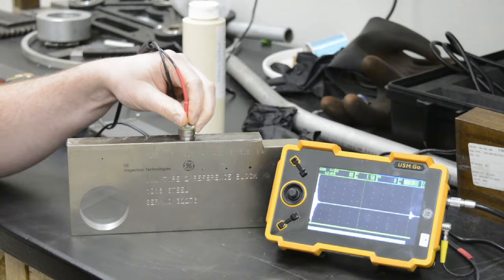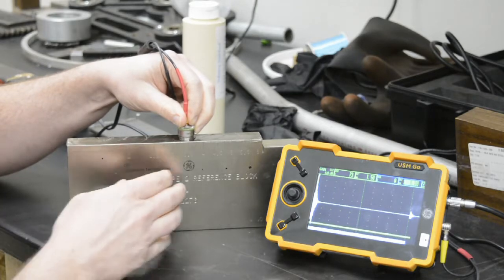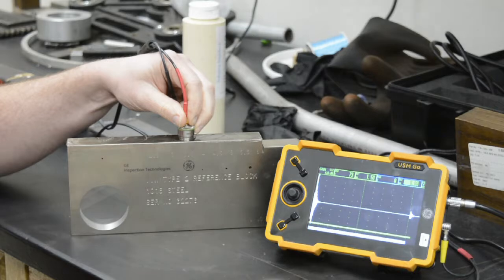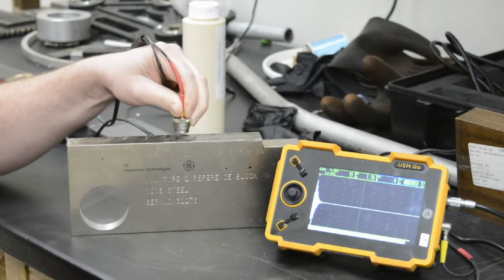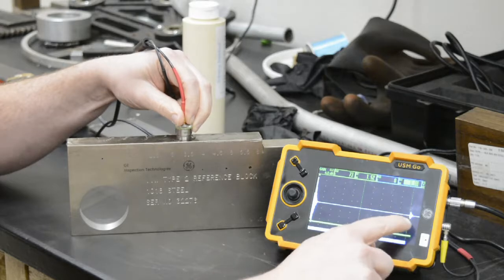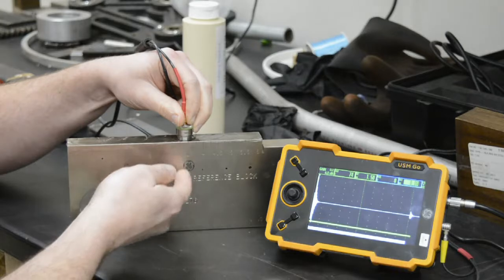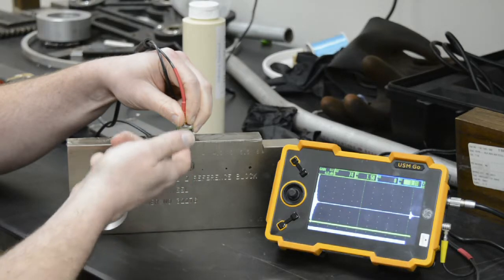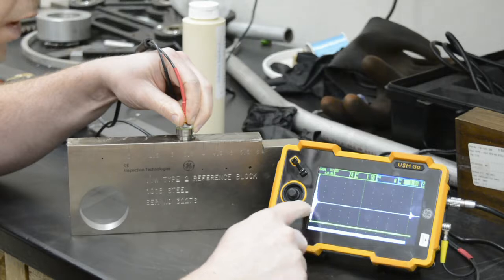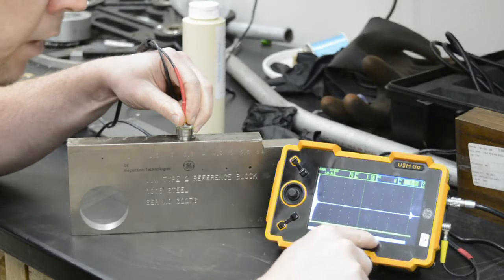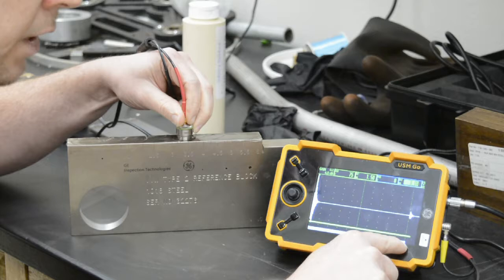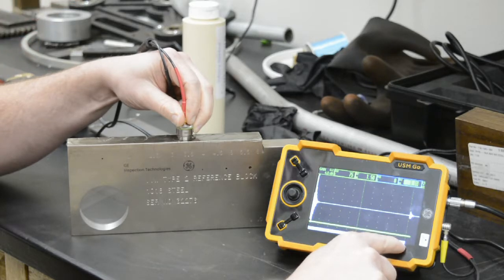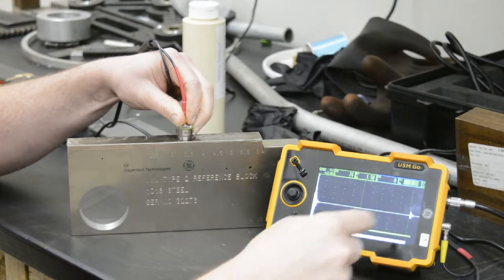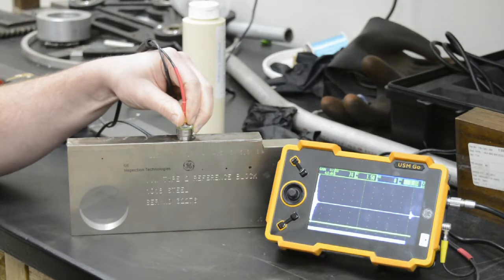So now, after putting the transducer against the surface of the block, the first thing we'll notice is these peaks here. I'm going to remove it here and put it back again. This represents the bottom of your sample. This is your back echo. That's the sound waves traveling to the bottom of the sample and then traveling back up. And this corresponds to the depth in the sample. The scale here corresponds directly to the range that we programmed into it previously. So this mark here is right at 101.5 millimeters.